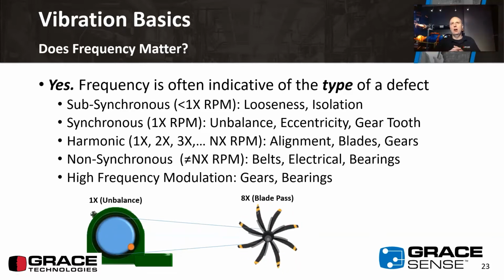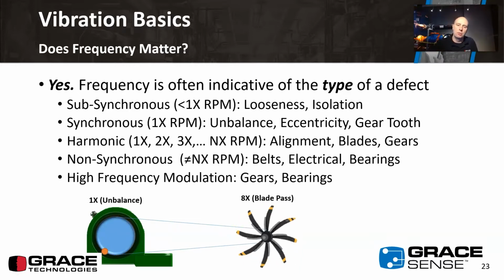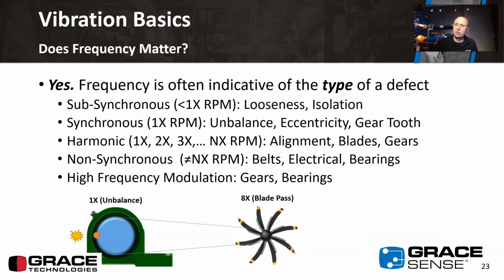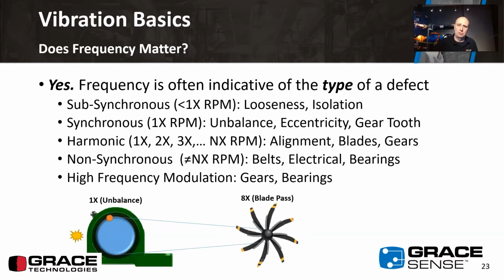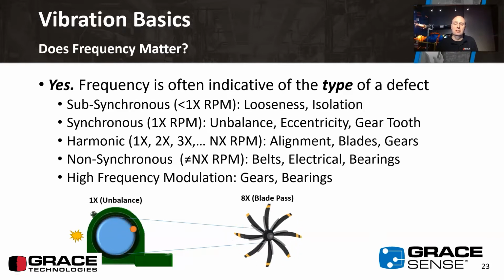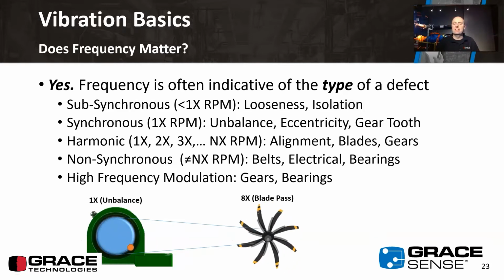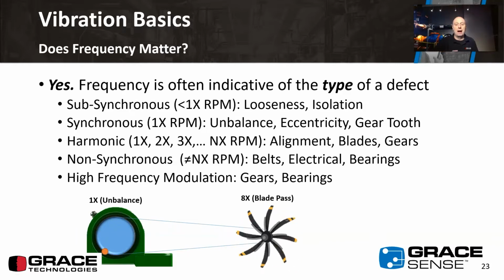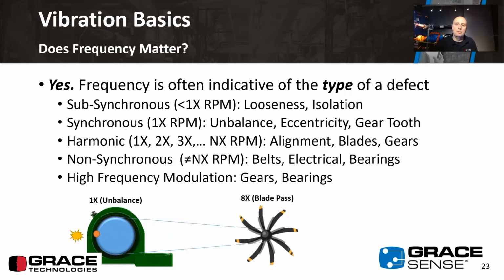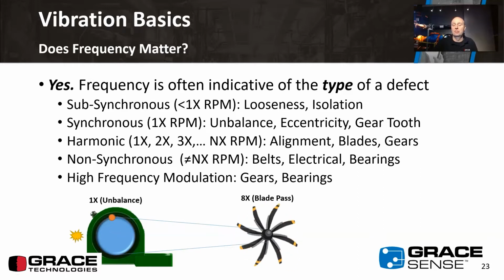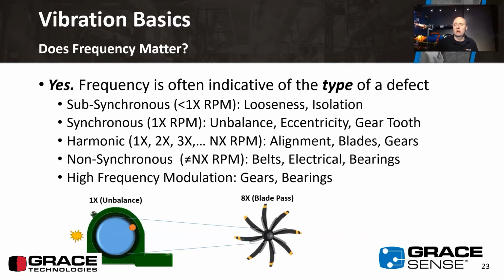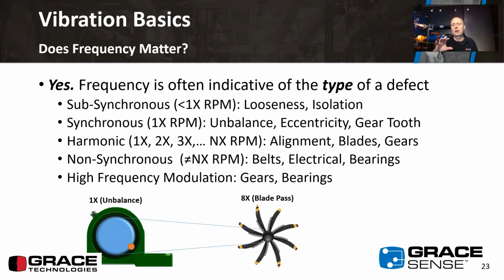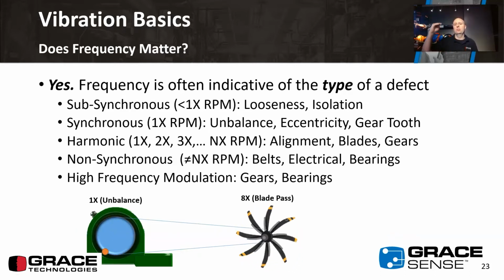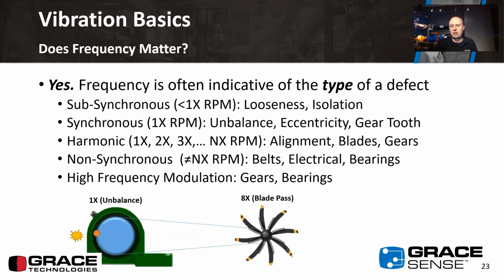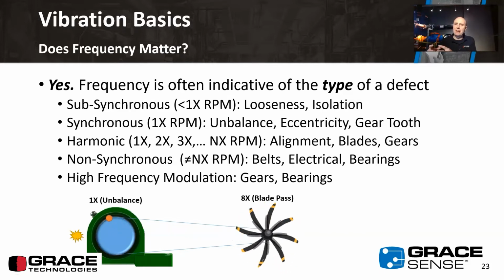So we typically break our frequency domain response of this rotating asset into a number of different bands: subsynchronous, which are less than the shaft speed; synchronous, which occur at that shaft speed; harmonic, which occur at multiples of that shaft speed; and non-synchronous, which occur at ratios not triggered by shaft speed. This can be things like bearing issues, electrical noise, or looseness—you might have a harmonic occurring based on the structural system, not the rotational speed. If we look at the high frequency modulation above that band, we start to really focus in on gear and bearing situations. It really matters where that defect is occurring—we'll get a different signal, and you'll see this clearly in the next few slides.